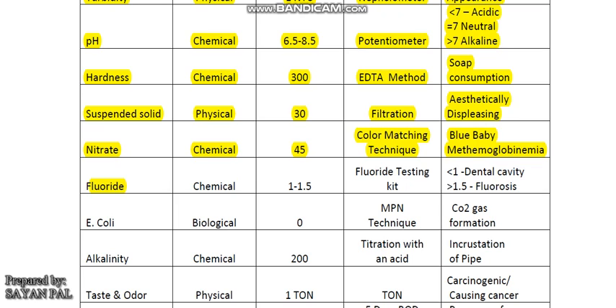Now fluoride. Fluoride is also a chemical water quality parameter and its limit is 1 to 1.5 mg per litre — the amount of fluoride in water should be effectively controlled. It is measured by fluoride testing kit. If fluoride is less than 1 mg per litre, it causes dental cavity. If greater than 1.5 mg per litre, it causes fluorosis. So the amount of fluoride in water should be controlled.